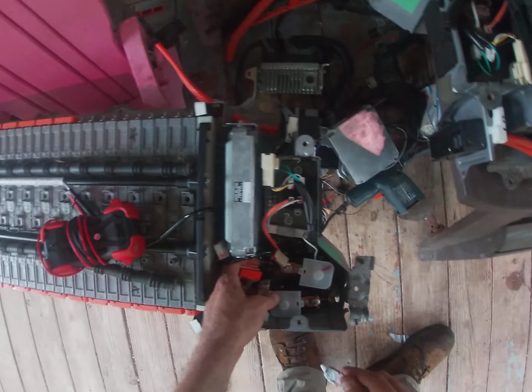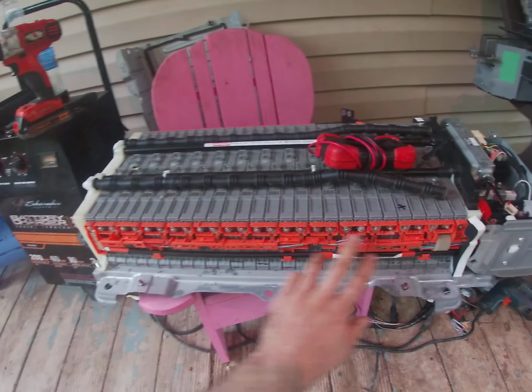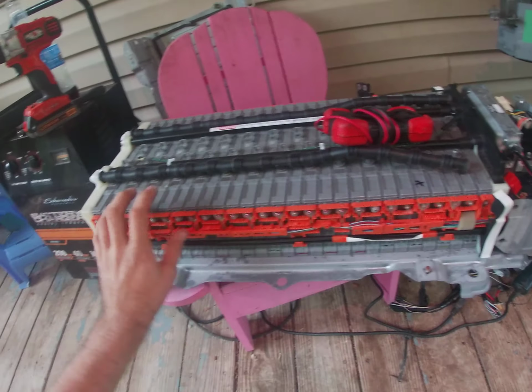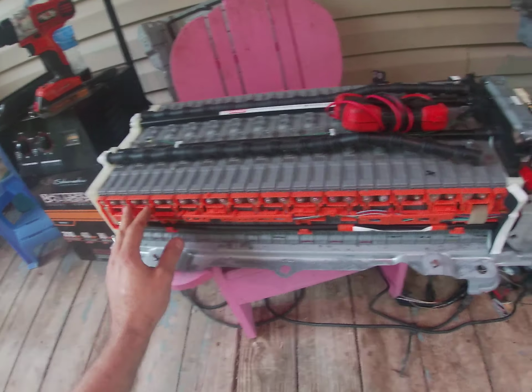You get like maybe 2 or 3 cell connectors that are bad on the cells, and then you've got to go through here and clean those out. But a lot of times when you're checking the batteries, I always take everything off and clean all of the bus bars before reinstalling or reassembling the battery. You've got a lot of corrosion on the nuts and stuff on the battery, so I'll clean those, and the copper bus bars will be polished before I assemble the battery pack.